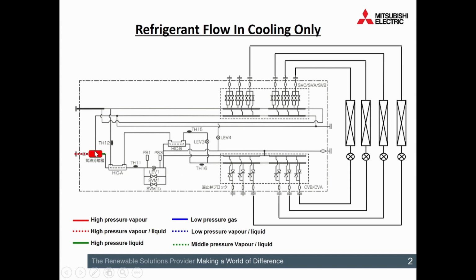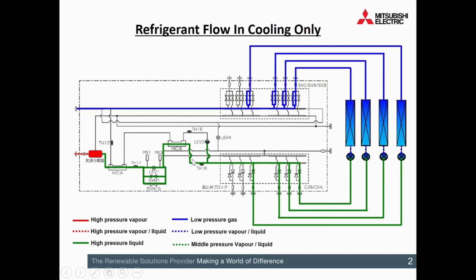So there's that refrigerant passing into the gas liquid separator inside the BC box. It looks like an enlarged bit of copper. And then we've got tube-in-tube heat exchangers here. So we're using our tube-in-tube heat exchangers to do that subcooling. So I'd expect it to be around about 20 degrees at TH16. So it'll have gone from say 35, maybe even up to 40 degrees, depending on what the outside temperature is. Through those tube-in-tube heat exchangers, subcool it, I say, to around about 20 degrees.